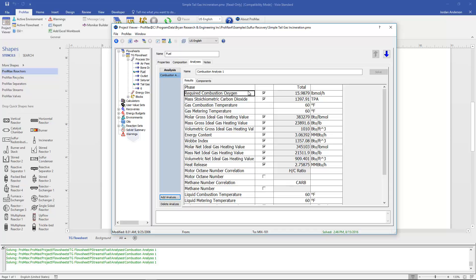The analysis is going to calculate the required combustion oxygen. So that's how much oxygen it would take to completely combust our stream. And along with that it will calculate a mass stoichiometric carbon dioxide, which is a mass flow rate of how much carbon dioxide would be generated in complete combustion.